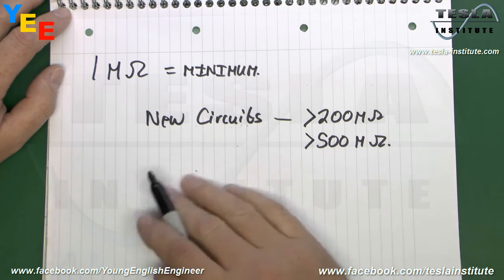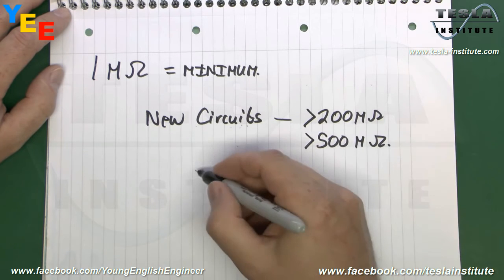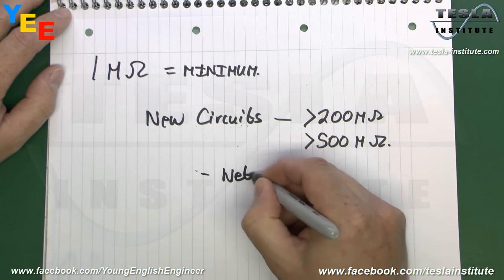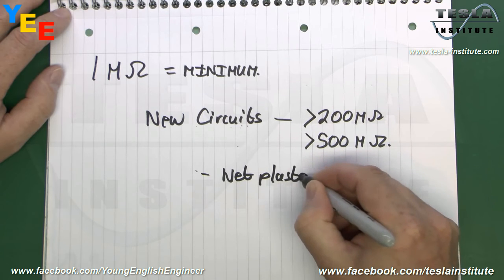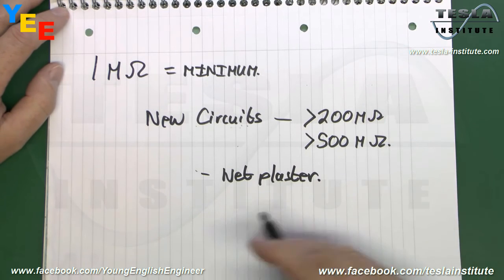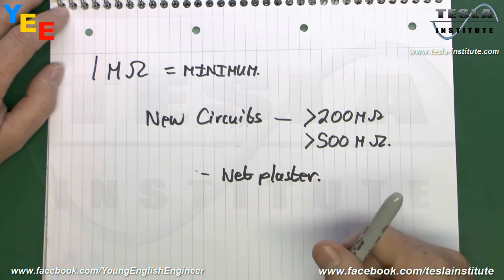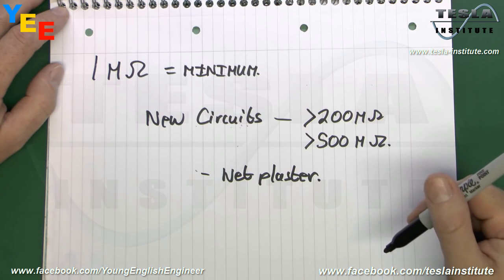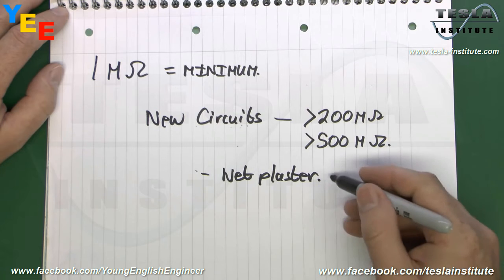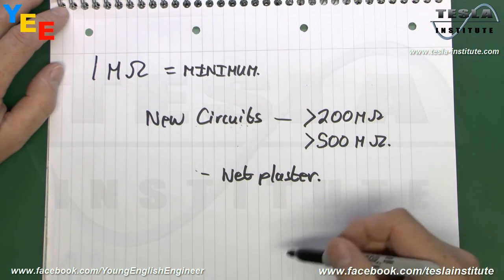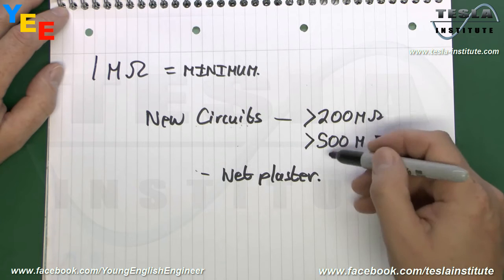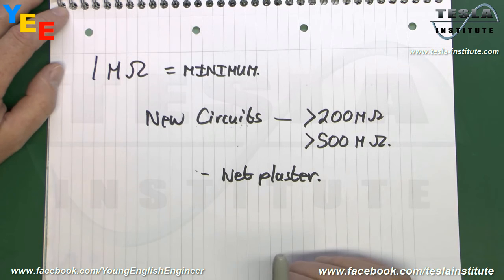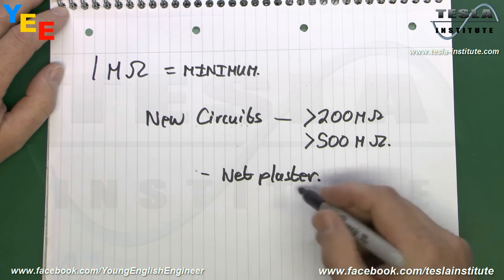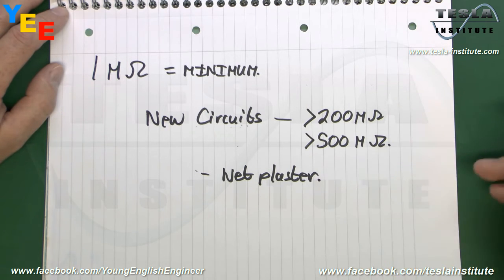If you find a new circuit that is less than this, then the most common cause is wet plaster. Say you've just rewired a house and the plasterers have come in, and of course there's a lot of dampness involved there. Some of that inevitably finds its way into the boxes and fittings, and bearing in mind the air itself will be fairly damp as well. So if it's only just been plastered and you get readings lower than this, it's more than likely due to the humid environment, or a bit of moisture has got in somewhere it shouldn't. But that should disappear after a few days. It certainly shouldn't remain around for any length of time.